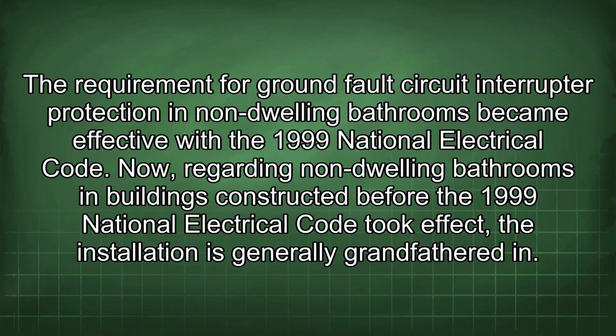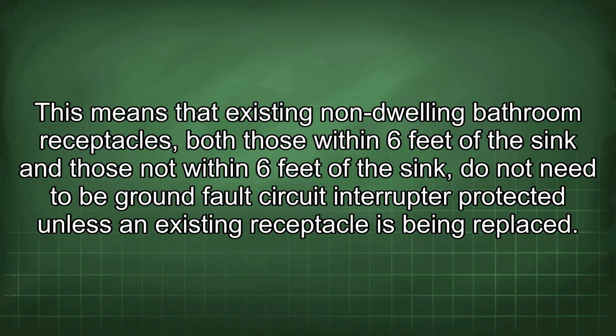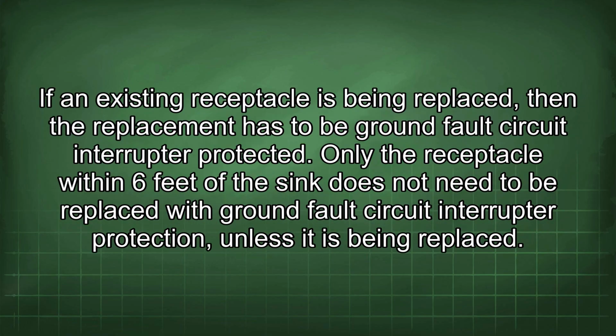The requirement for ground fault circuit interrupter protection in non-dwelling bathrooms became effective with the 1999 National Electrical Code. Now, regarding non-dwelling bathrooms in buildings constructed before the 1999 National Electrical Code took effect, the installation is generally grandfathered in. This means that existing non-dwelling bathroom receptacles, both those within 6 feet of the sink and those not within 6 feet of the sink, do not need to be ground fault circuit interrupter protected unless an existing receptacle is being replaced. If an existing receptacle is being replaced, then the replacement has to be ground fault circuit interrupter protected.